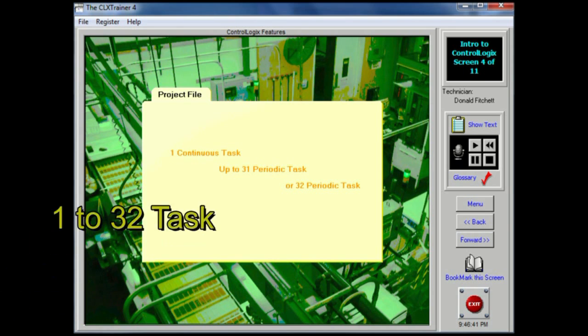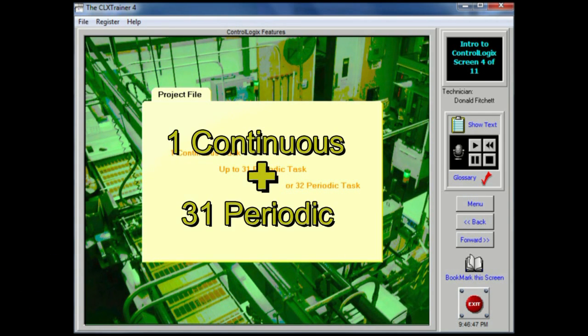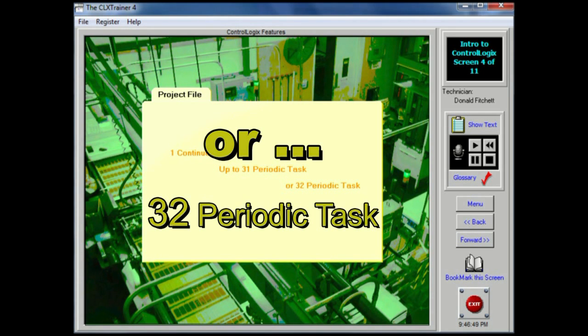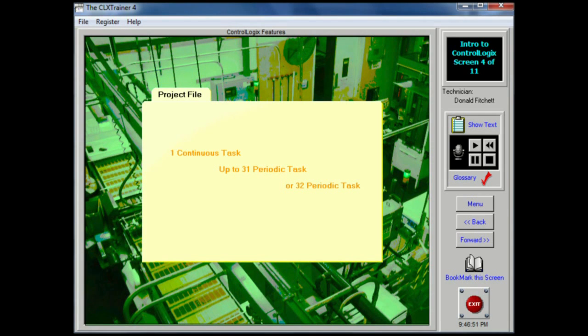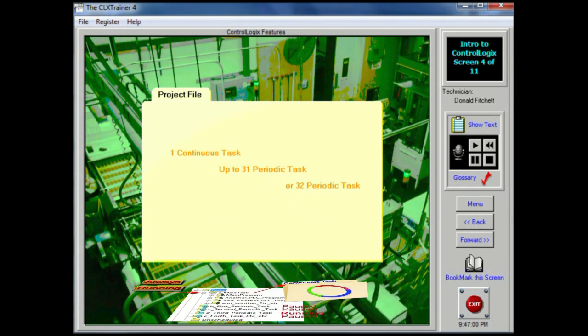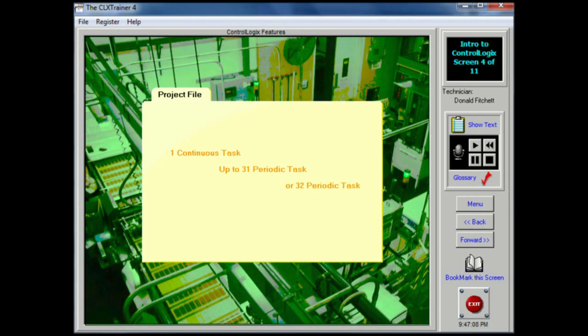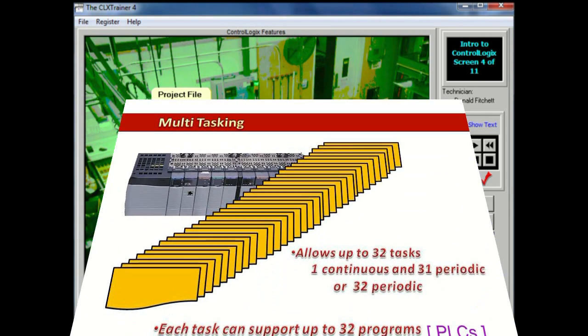Multitasking and multidiscipline: this feature allows the controller to handle up to 32 tasks — one continuous and up to 31 periodic, or simply 32 periodic. A task provides priority and scheduling information for a set of one or more programs executed based on a specific set of criteria. These tasks operate as interrupts so the controller will suspend execution of the current task to perform the called task. Each individual task can schedule up to 32 programs.